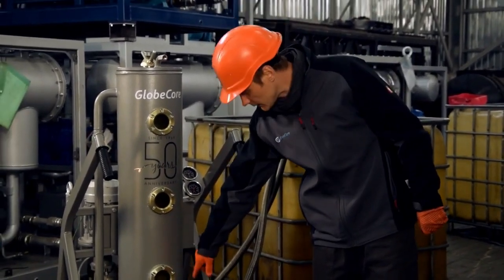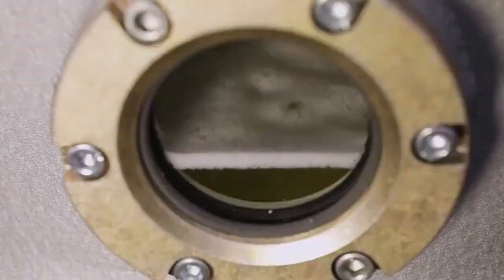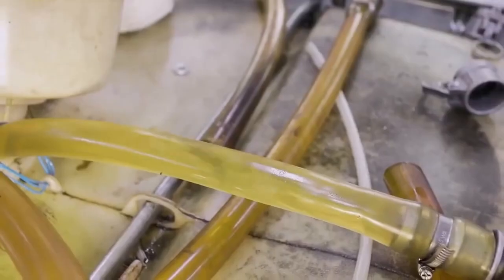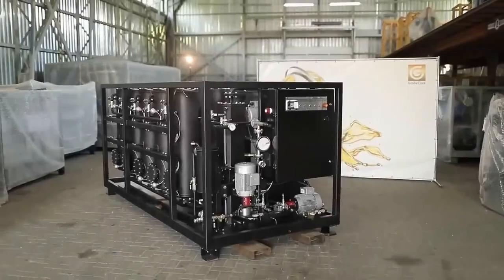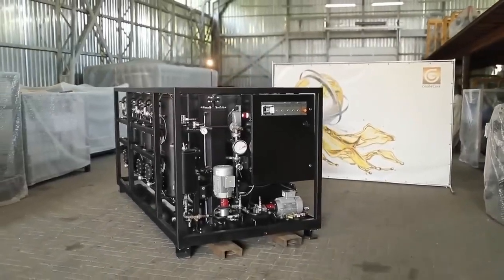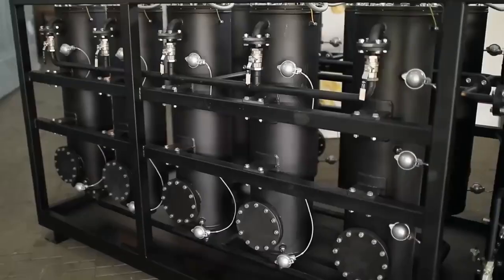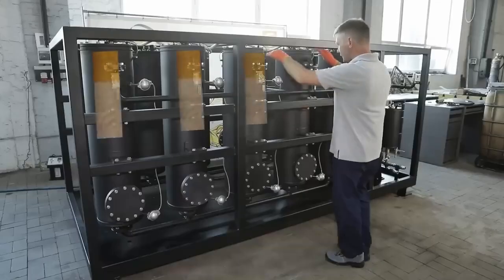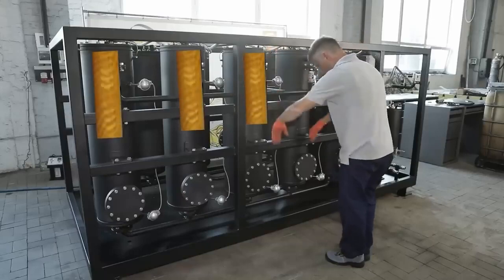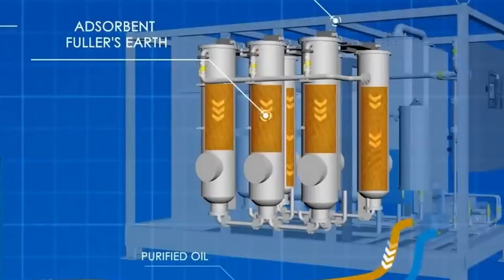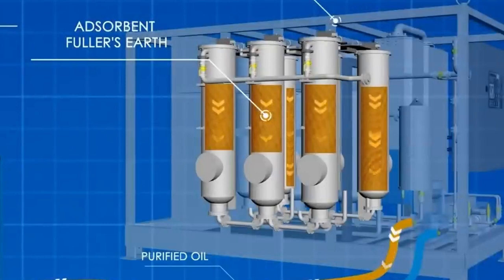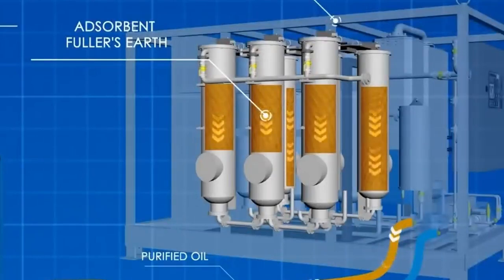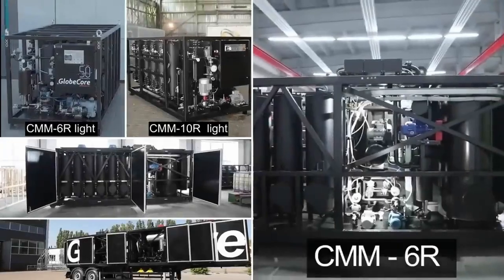At the second stage, the turbine oil is fed into the CMMR machine, where adsorptive purification takes place. Turbine oil is run through columns filled with a sorbent; meanwhile, the sorbent absorbs all decomposition and aging products into its granules.